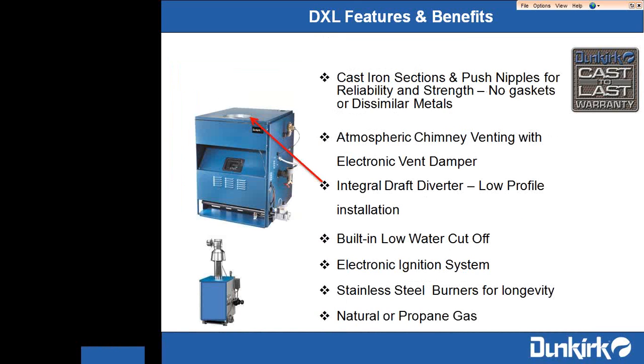The next product is our DXL. This is also a product that has been brought into inventory. The DXL is our mid-efficient, 82 and above percent atmospherically vented cast iron boiler. I'll start off by saying that every Dunkirk boiler is made from cast iron boiler sections joined by cast iron push nipples. We don't use rubber gaskets, such as companies like Weil-McLain or H.B. Smith use, and we don't use steel push nipples like Buderus or Slantfin use. We stick with cast iron because that's what the sections are made out of, and the cast iron push nipple will expand and contract at the same rate as the boiler section, giving us a nice tight seal in between sections.